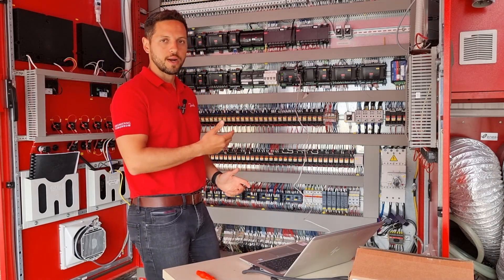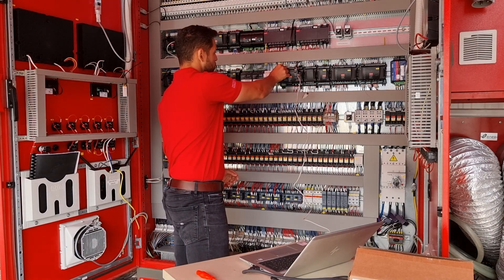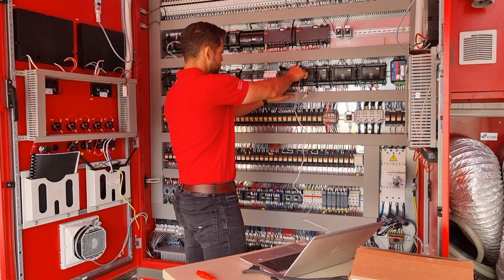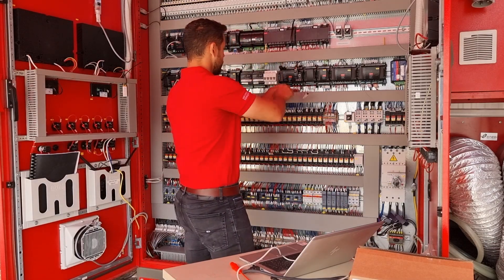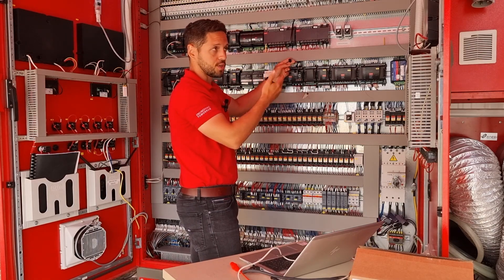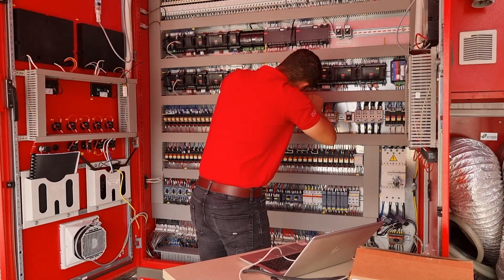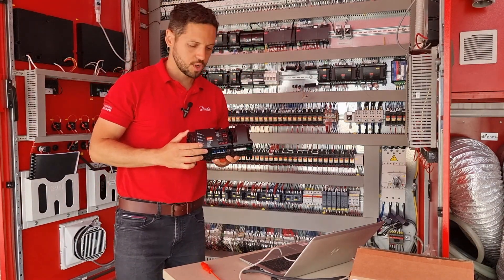First of all, ensure that your AK-PC 782A is turned off. I will turn off the 782A and of course the next step is to take out the connectors. I will start with the USB connector — we just used it to extract the database. I will also remove the LonWorks connector because we will no longer use the LonWorks connection to the system manager. We will now use the IP connection.